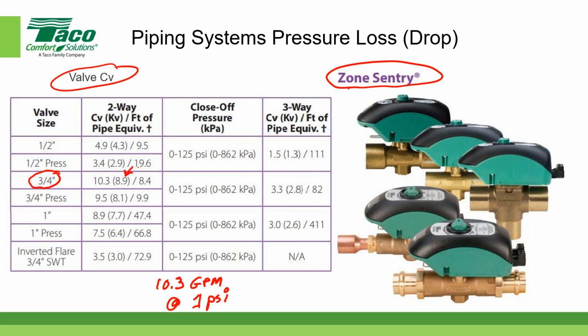Isn't that cool? Now that's a two-way valve. And if you notice over here on the right-hand side for our three-way valves, we have the same set of values. The first one's a CV, the second one is KV, and the third one is equivalent length of feet. Very cool stuff. And then you need to convert the 1 PSI into feet. Yeah, but most of the manufacturers will give you that information, so you don't have to worry about it. But if it's feet, 1 PSI is equivalent to 2.31 feet.